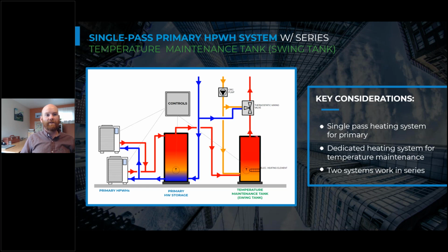The volume of this tank, how big it is, is directly associated with how many hours of the no use period we can coast through. So if we have a very large volume, we can coast through a longer no use duration. If we have a very small volume, we're not going to be able to coast through much of that no use duration.